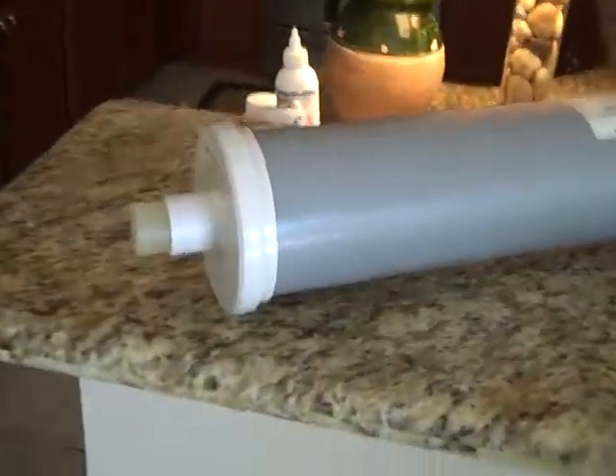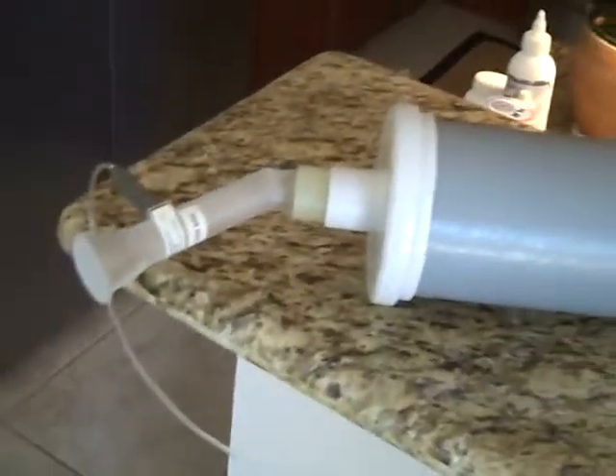At the beginning of each day, you have to do a calibration check. You only have to do it once, and then you include a copy of it with any test that you do that day. But the hard plastic piece should fit right down into the end of this calibration syringe. You have to squeeze it a little bit to get it in, and you see how it sits in the calibration syringe. And you go to the machine, you turn it on, and it will go through a self-test, and then it'll say self-test in progress, and then proceed.